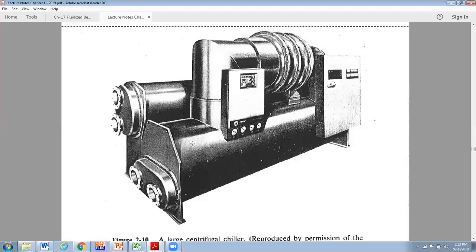They're not typically, because the temperature of those things is up in the 80 to 90 degrees, maybe upper 70s, and so you don't have any condensation to worry about, and so you don't typically insulate those. Centrifugal compressor up here, control module, electrical panel, bringing the power in, distributing it out to the unit. We'll probably have some videos that talk about more details on this, but that's kind of what they look like.